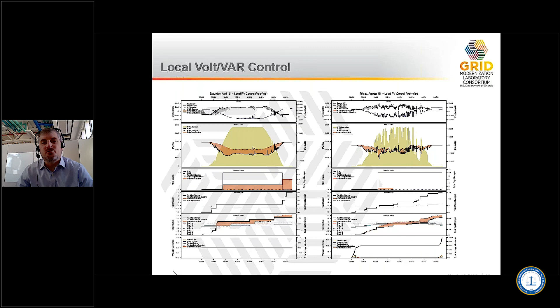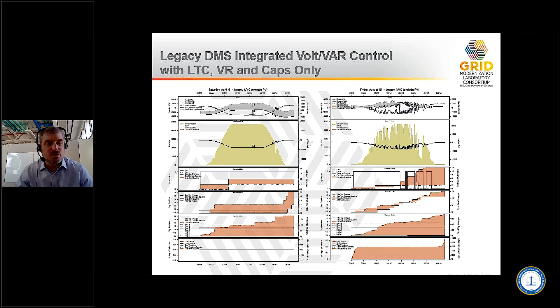Now we start looking at ADMS implementation. In this case it's legacy, meaning the ADMS is controlling the legacy equipment. What you can see immediately is a huge amount of red, which is really good — it means we're dramatically reducing the number of capacitor bank operations and reducing that wear-out factor, while still regulating voltage at the customer as required. So even with basic ADMS operation, there's a massive reduction in the overall impact on the circuit, even on the really variable day. This is a really good sign.